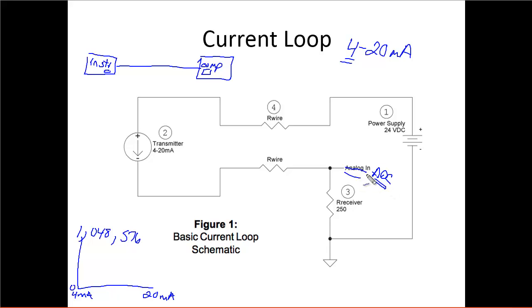So at this point, I'm actually reading a voltage, you know, analog to digital converters, you pretty much always put a voltage in there. And I'm just reading the voltage here. So now I have a voltage going into my analog to digital converter card that is proportional to the output of this transmitter. But I'm not just using a volt, I'm not just reading the voltage directly, I'm going through this current loop setup, which is more and more immune to noise and also can compensate for the resistance in the line for me. And then again, it also gives me the advantage that I can tell when there's nothing hooked up to it.